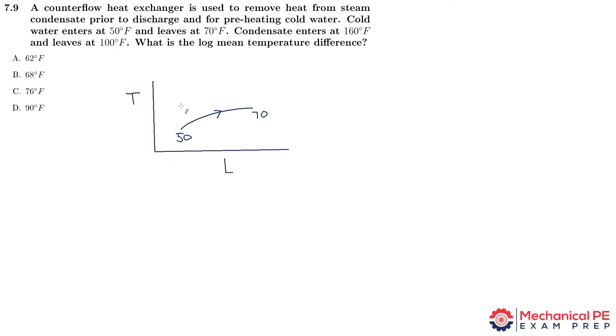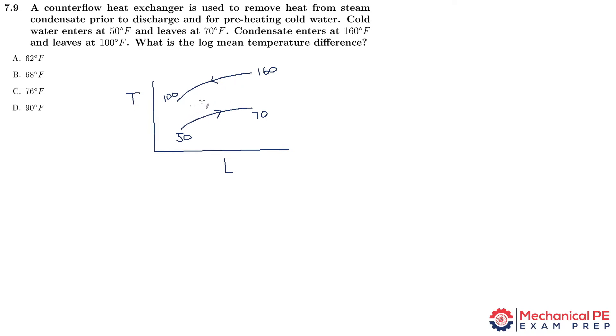But now that we know it's counter flow, it's going to be the opposite direction. So we draw it going to the left instead — the opposite direction — where this side is 160 and this side is 100. What that does is it keeps the delta T along the length of the heat exchanger closer to the average delta T.